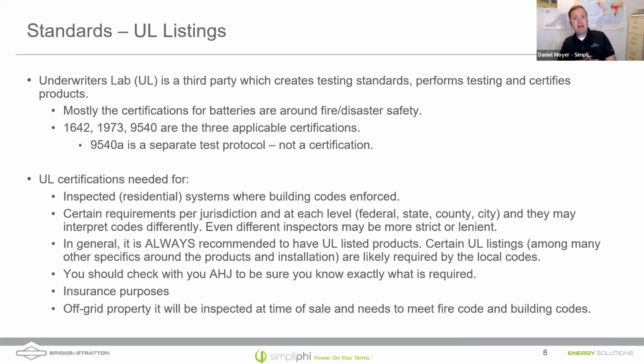We talked a little about these UL listings, so let's jump a bit deeper into that. 1642 is on the cell level, 1973 on the battery module, 9540 on the system level. And then 9540A comes into play as a large-scale fire test. We take one of our energy storage systems and send it to a UL lab, and it's not just any lab doing these 9540A tests, but they're kind of the big name here.